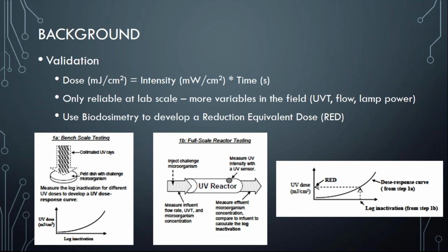And you can kind of see on the figure to the right, you relate that log inactivation to a reduction equivalent dose. And this basically just is a verified way to know how the system is performing in the field.